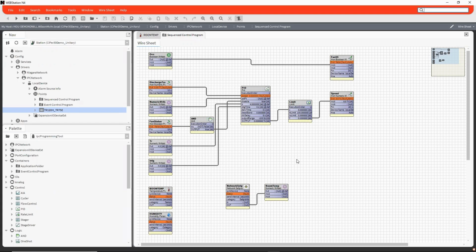If you have min-max flows, set points, things like that, you can pre-configure all of that and then take that spreadsheet, push it back into one of your main CIPer30 controllers, and then from there, it'll create all of those different station files for you, and then you just load them into that CIPer30 and you're good to go.